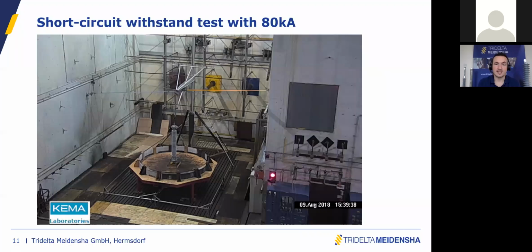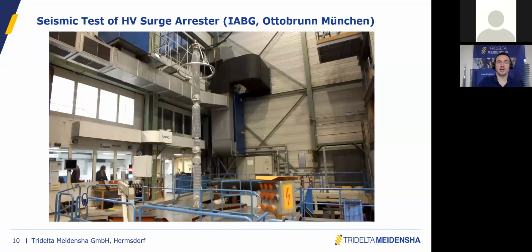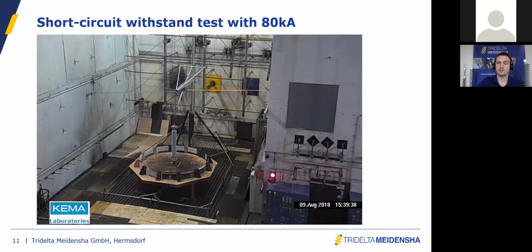Basically, with this hollow core design, because of its robustness, you can achieve very high short circuit capabilities, up to 80 kA in that case, because this is a requirement for the German utilities and also in Canada. You can achieve very high short circuit values without significant damage on the housing. And of course, for the seismic application, you can fulfill almost all requirements depending on the diameter and the size of the tube. We have to find a solution for those videos.